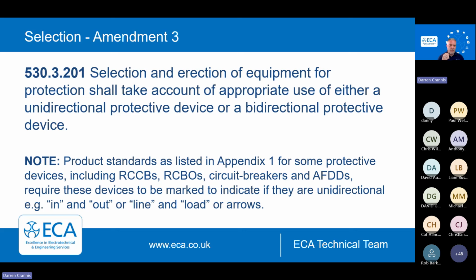That is obviously important now because energy can go both ways. Battery storage systems are a classic example. They're importing and exporting all the time. With solar PV, when inverters first start up, they're actually current using, looking at the grid first, and then they go backwards, hopefully, with some good, free, cheap energy. The worry there was that if there was a fault and the RCD did disconnect, there might be some voltage sat on the top terminals and it might damage the RCD. So that's why it's important that we look at the direction of energy when it comes to things like heat pumps, vehicle to grid, solar, and other generation, and that we select the right device.